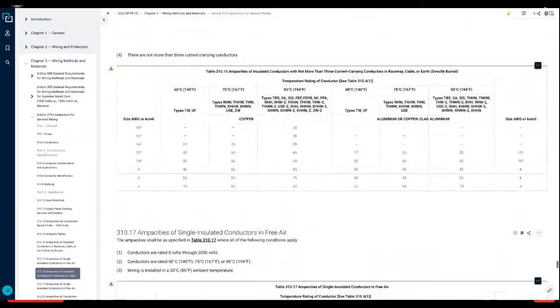Yeah. Okay, so I expand the table here. Let's say I go with 246. That wouldn't be enough. So we'll go with parallel 3 times with 250. 255 times 3, that's not enough. We'll say we do it at 4 times. That's too much. Let's see, 230. Yeah, that'll work. So say we take a 4-aught parallel at 4 times, 75-degree terminals, that's 230 amps. You take 230 amps parallel at 4 times, that gives you 920 amps. That's right above the 905 amps. The conductors have to be equal to or exceed the overcurrent device.